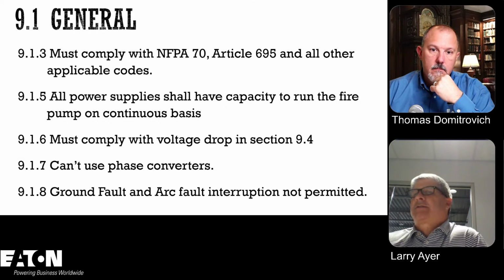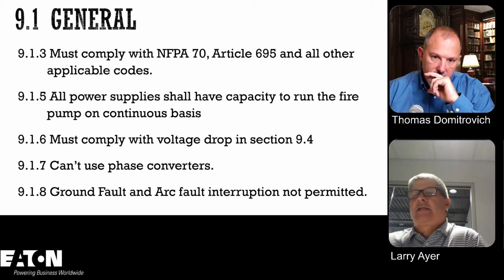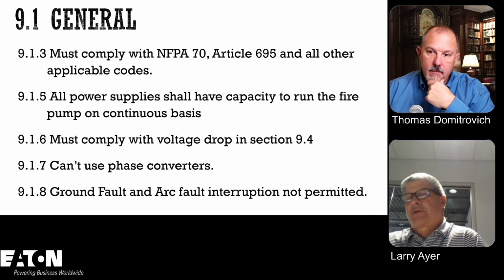9.1.5. That's one of the keys, right? We need to have power supply shall have the capacity to run the fire pump on a continuous basis. You must comply with the voltage drop in section 9.4. You can't use phase converters, and you can't use ground fault and arc fault circuit interrupter protection.